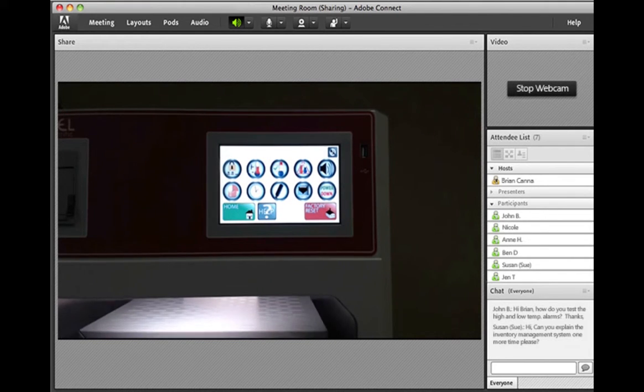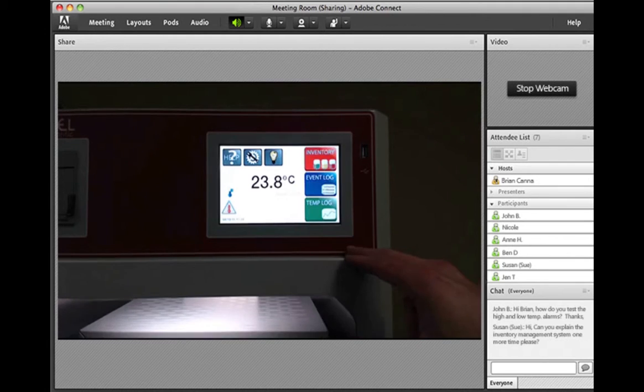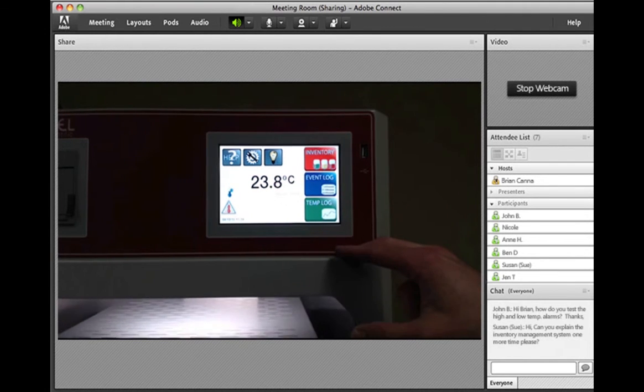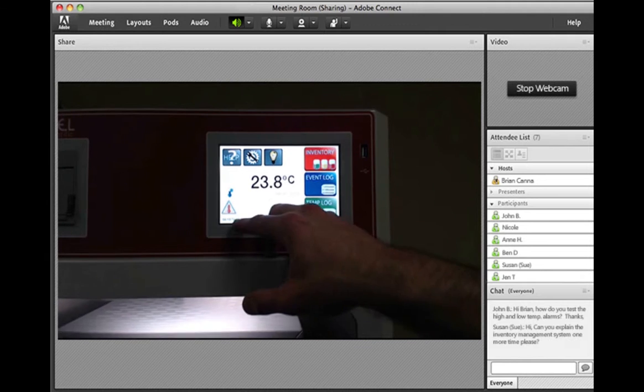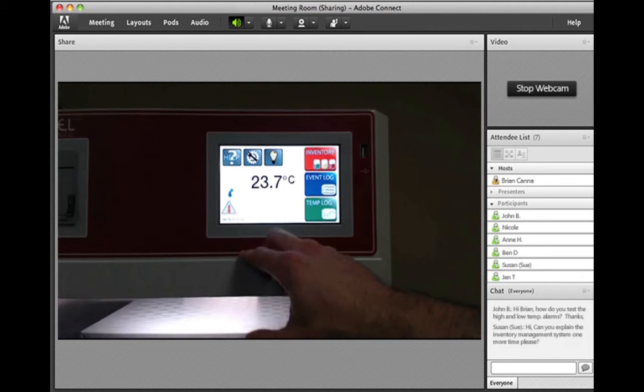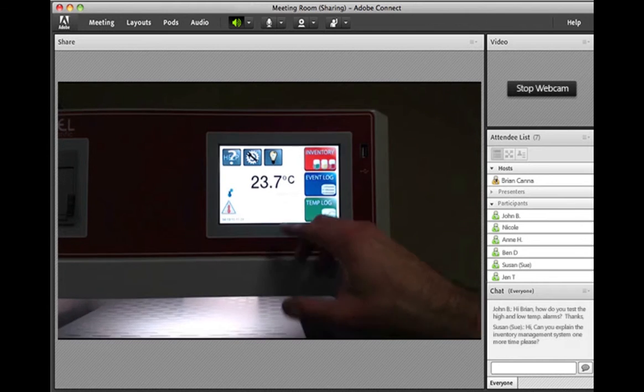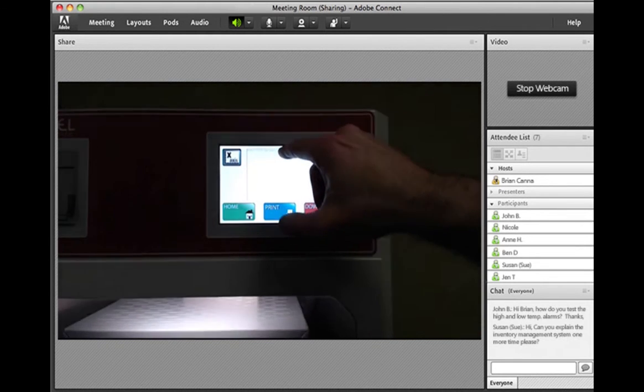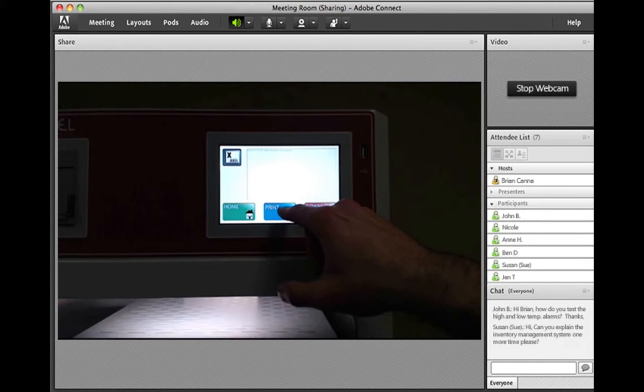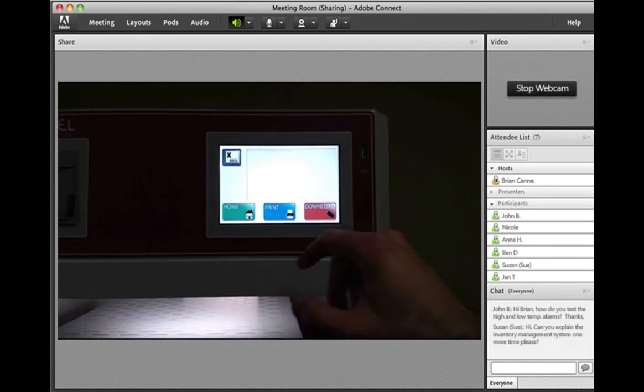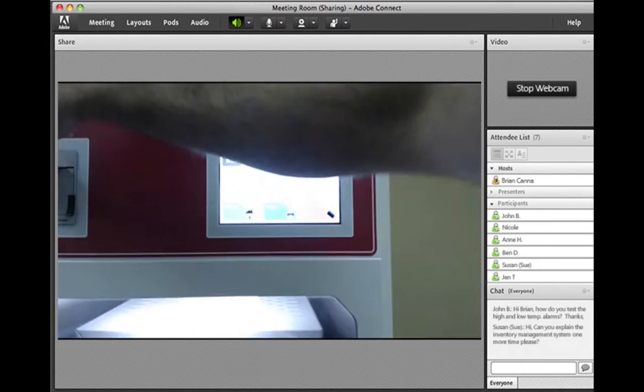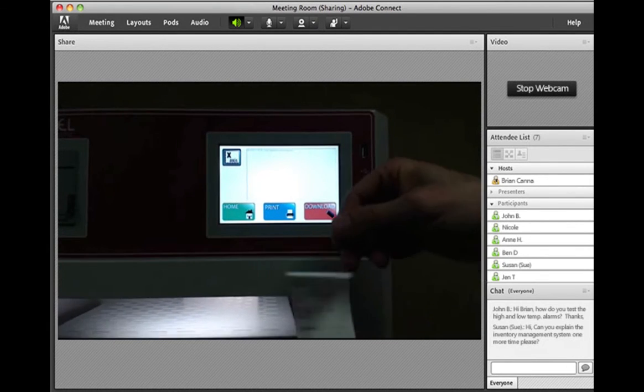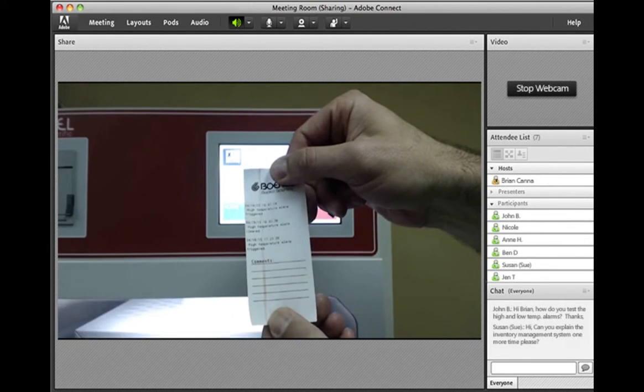So it looks like Sue has a question about the inventory management system. Just wants me to run through that one more time. So we'll go back out to the home screen. We can see that the temperature is elevated because of the last test. We have our high temperature alarm right there, and you can see it's grayed out because we cleared it. It will be on the event log. See, high temperature alarm triggered right there. If we want, we could actually print that out. So we have our high temperature alarm right there, and it was cleared.